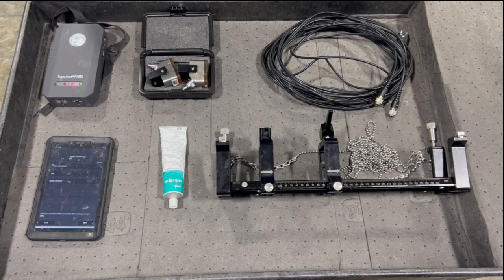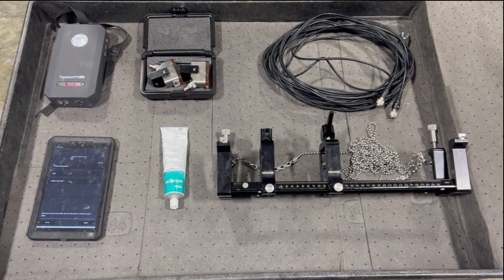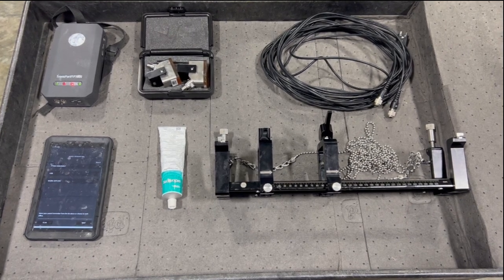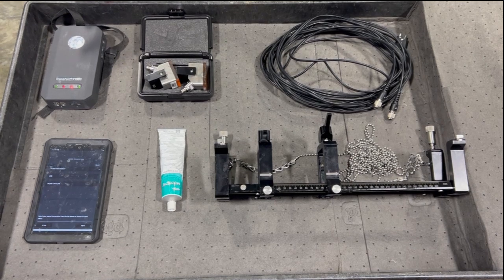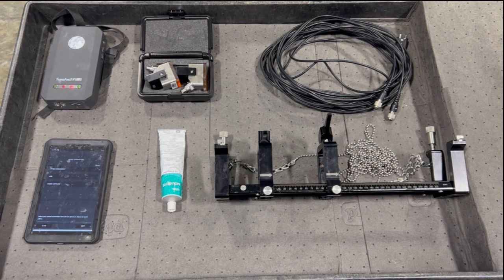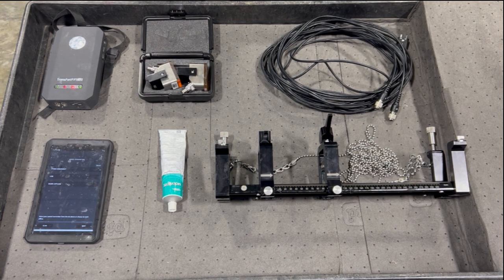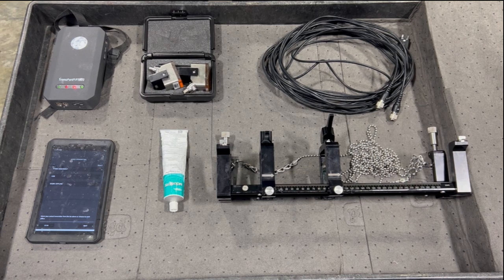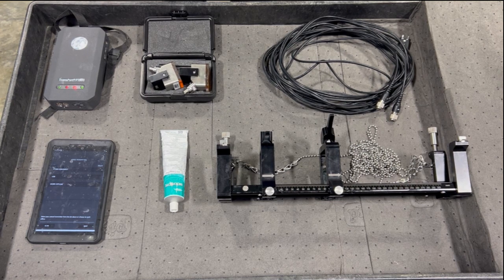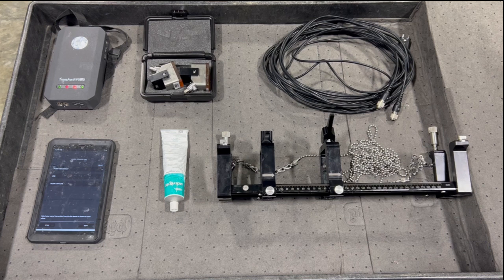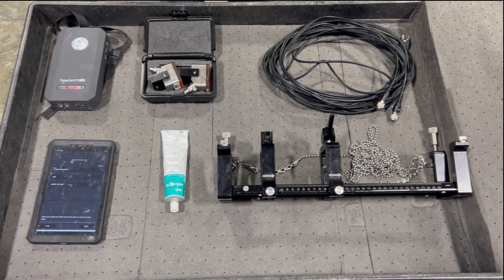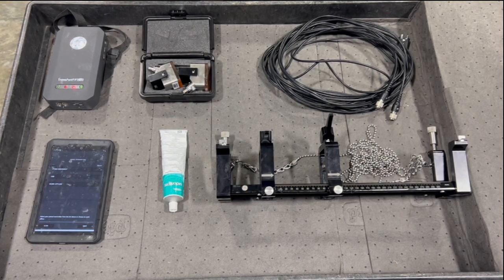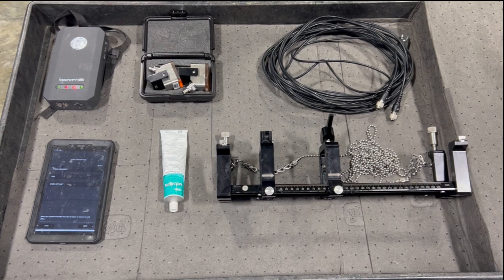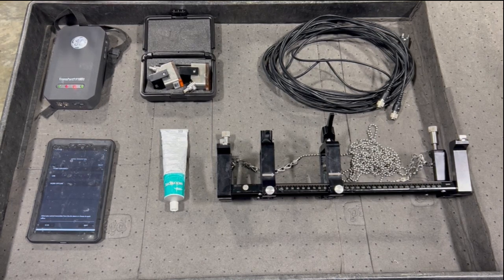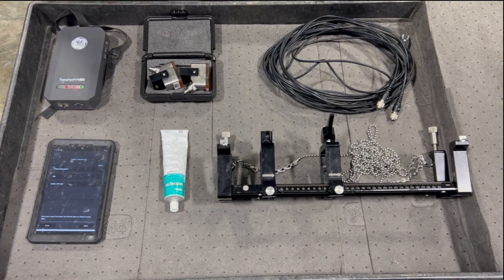Flow meters can be stationary, monitoring flow in a header manifold on your system. They can also be mobile, like this GE Transport PT900 flow meter we have here. We like to use a mixture of stationary flow meters for critical flow on your system, but also have the mobile flow meter around so that you can bring it tank side and get flow rates from pipes as low as ½ inch to 24 inches in size. So let's go through and take a look at what all comes along with having a mobile flow meter here.